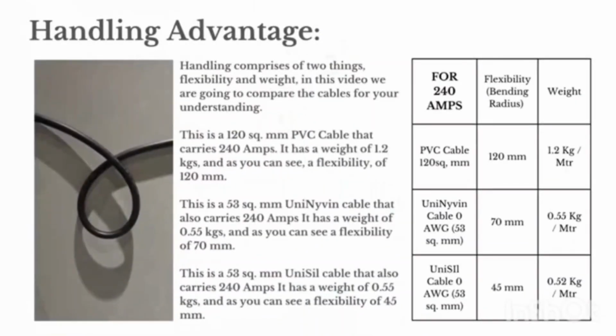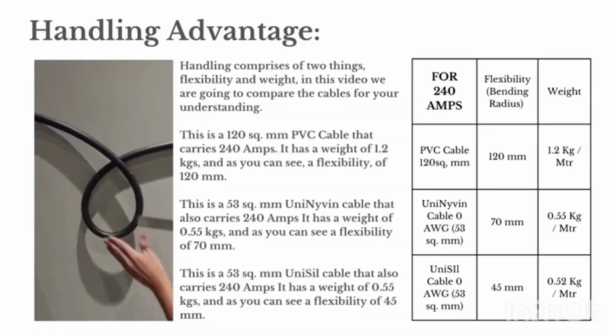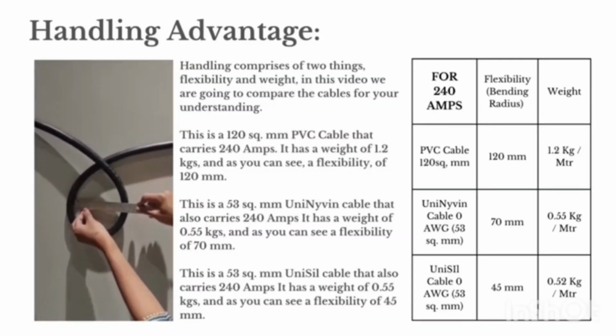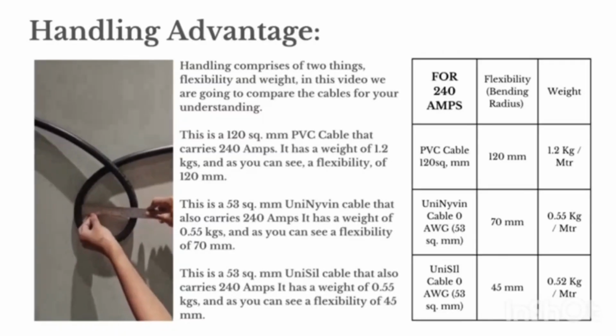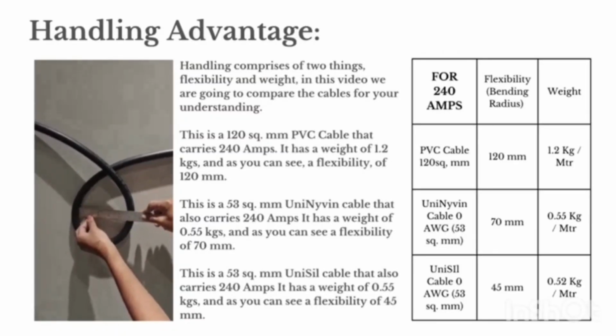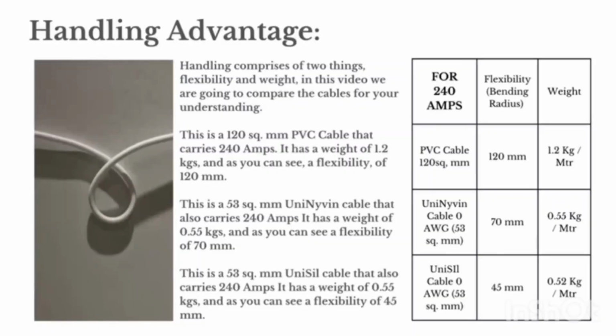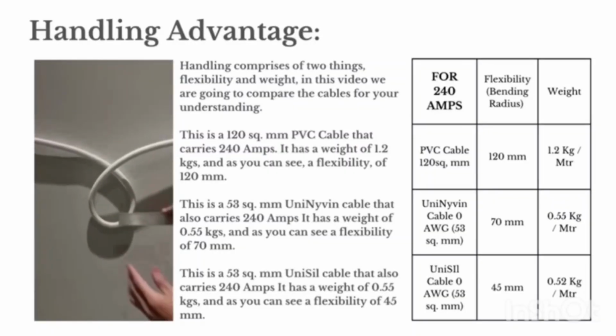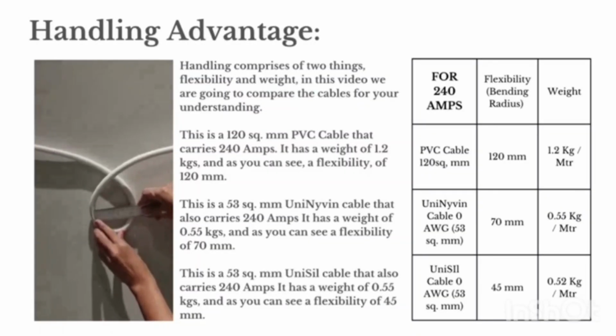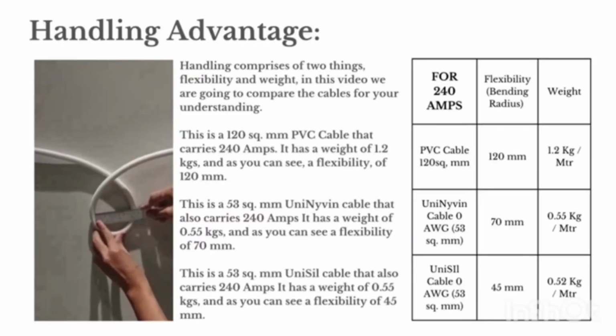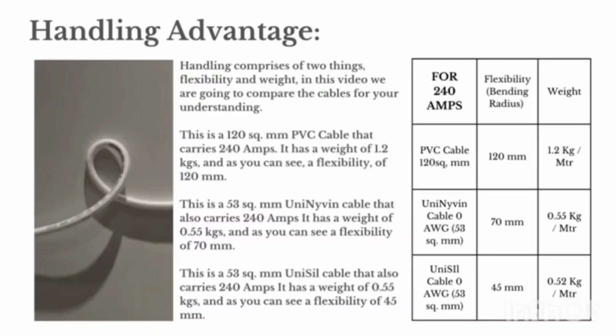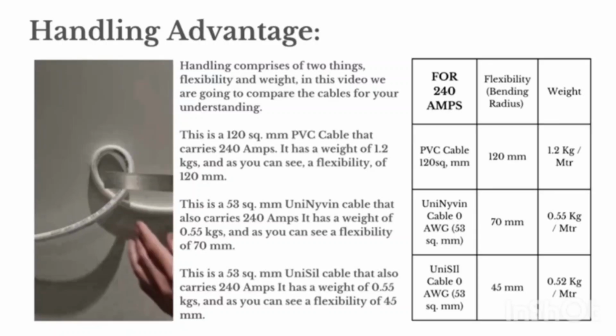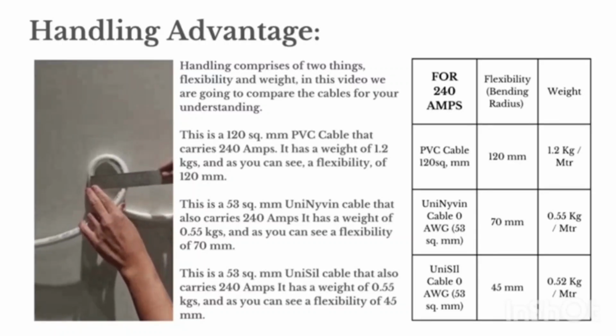Handling advantage. Handling comprises of 2 things: flexibility and weight. In this video, we are going to compare the cables for your understanding. This is a 120 square mm PVC cable that carries 240 amps. It has a weight of 1.2 kgs and, as you can see, a flexibility of 120 mm. This is a 53 square mm UniNyvin cable that also carries 240 amps. It has a weight of 0.55 kgs and, as you can see, a flexibility of 70 mm. This is a 53 square mm UniSil cable that also carries 240 amps. It has a weight of 0.55 kgs and, as you can see, a flexibility of 45 mm.